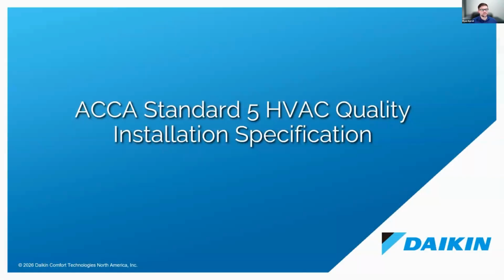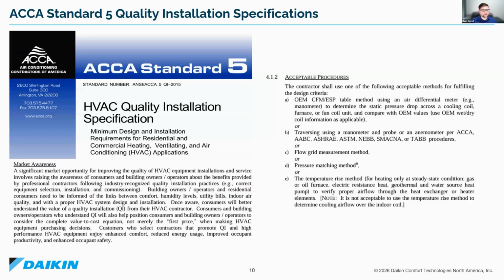What is that specification? ACCA Standard 5. ACCA Standard 5 has been out for quite a while, but this actually defines what a quality installation looks like. That's the acceptable procedures for measuring airflow. I listed all those common installation faults, and a lot of them had a theme, and that was airflow, sealed ductwork, and basically what Steve and Joe were talking about, and the tools they have to be able to measure this is something that we don't always have access to. So to be able to do this with the tools we have today, it's just a huge advantage.